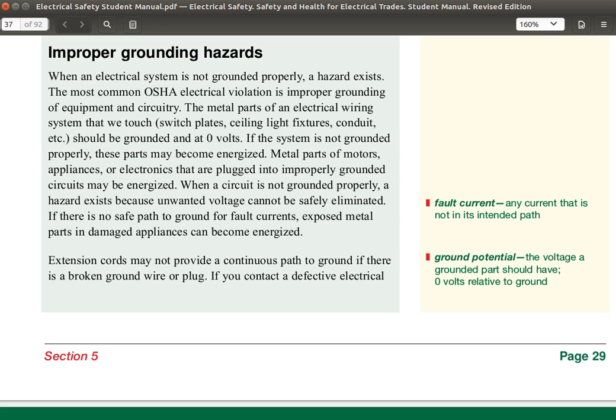When a circuit is not grounded properly, a hazard exists because unwanted voltage cannot be safely eliminated. If there is no safe path to ground for fault currents, exposed metal parts in damaged appliances can become energized. Extension cords may not provide a continuous path to ground if there is a broken ground wire or plug.